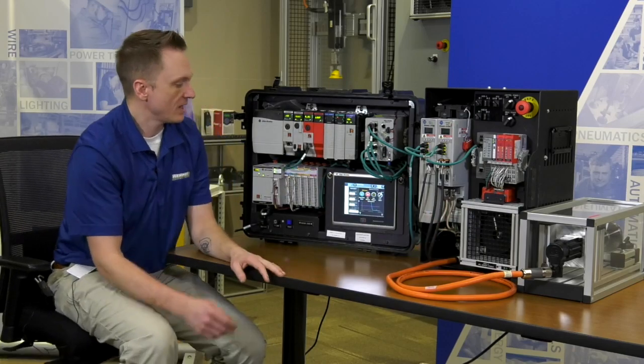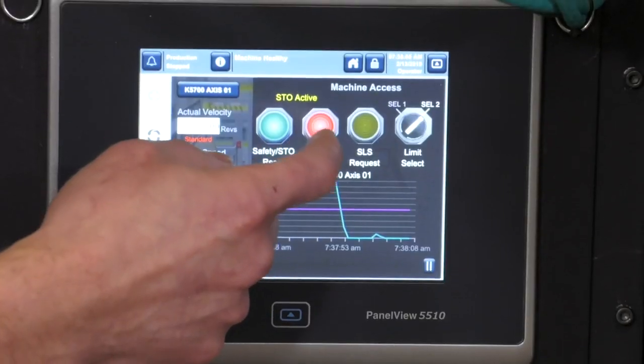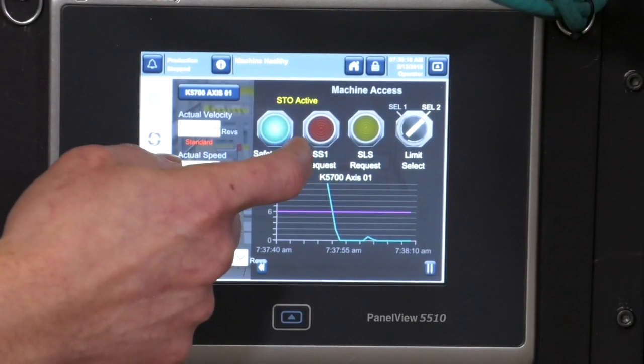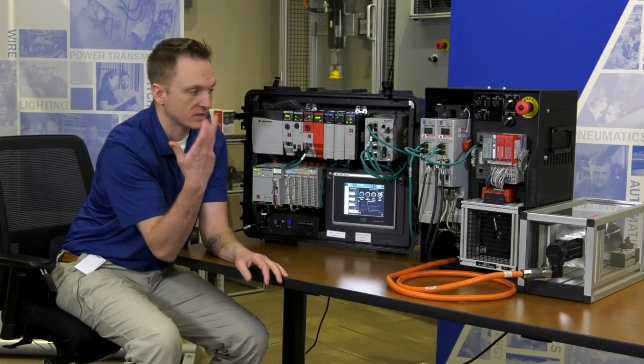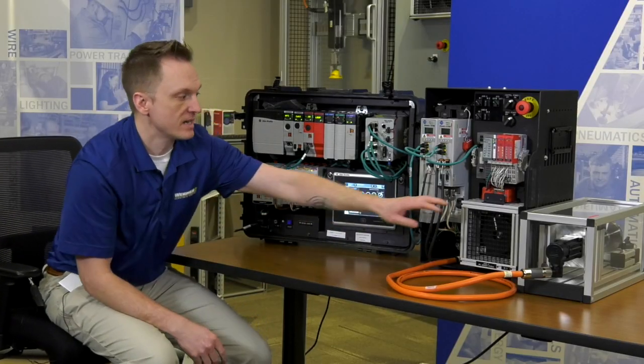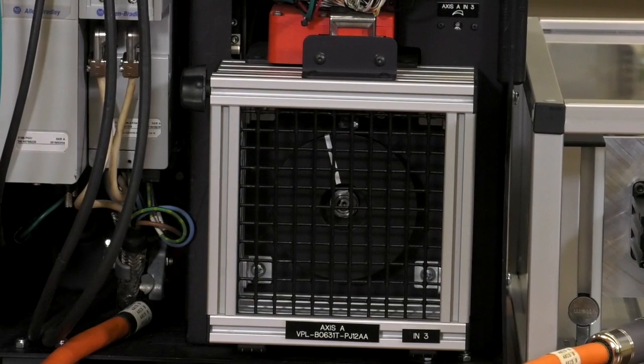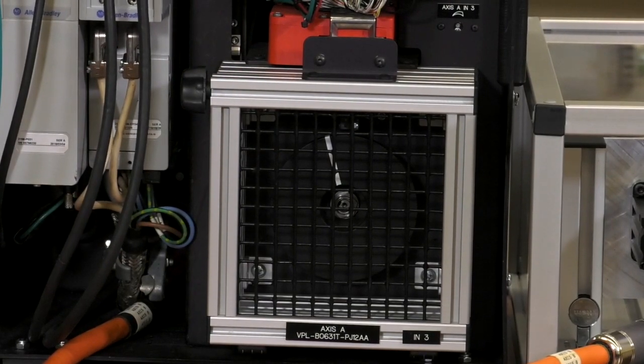I close it back up, and I clear those two requests, Safe Stop 1 and Safe Torque Off. You'll hear the click, it goes back in, it's now in a safe state. I can interact with it again, and I'm ready to go, so I'll go back to motion.